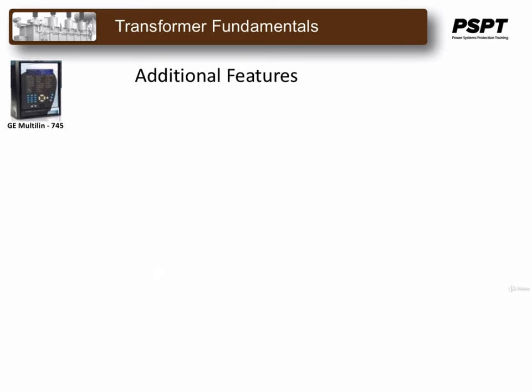Additional features for the 745 include negative sequence overcurrent. For delta-Y impedance grounded transformers, overcurrent protection is particularly difficult to set. A negative sequence-based overcurrent element provides the required sensitivity.